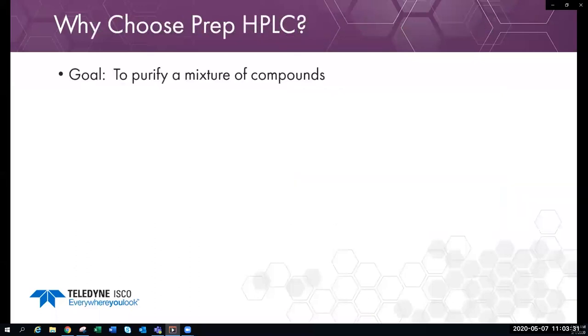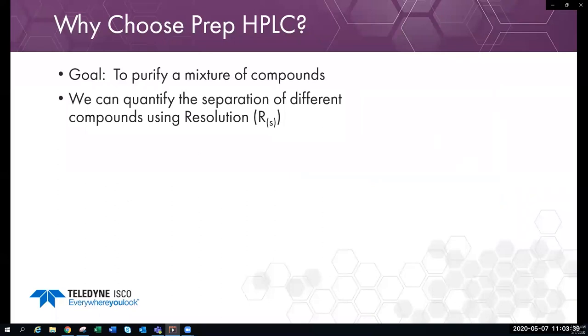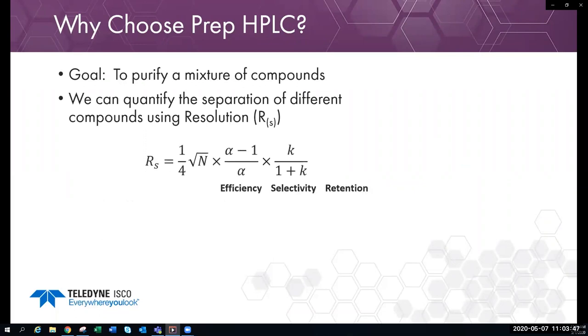So why choose prep HPLC? Our ultimate goal is to purify a mixture of compounds — to get our target compound as pure as possible. To quantify the separation of different compounds, we use resolution. The equation for resolution consists of three components: the N value refers to efficiency, the alpha component is selectivity, and the portion consisting of K represents retention.